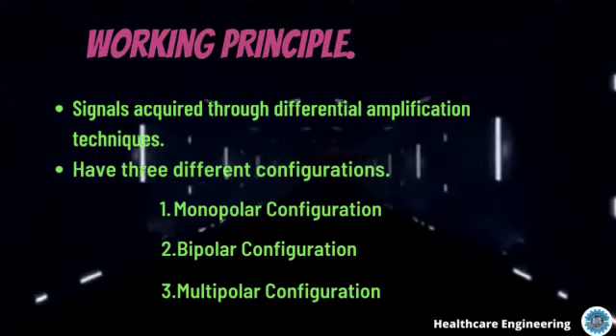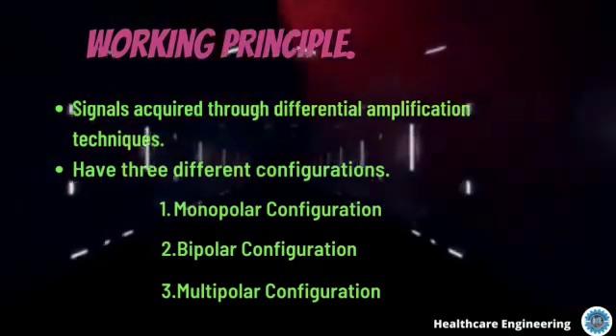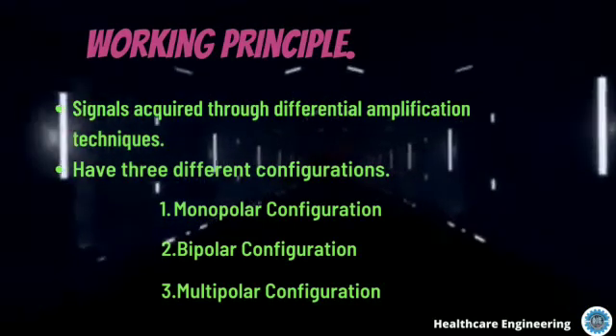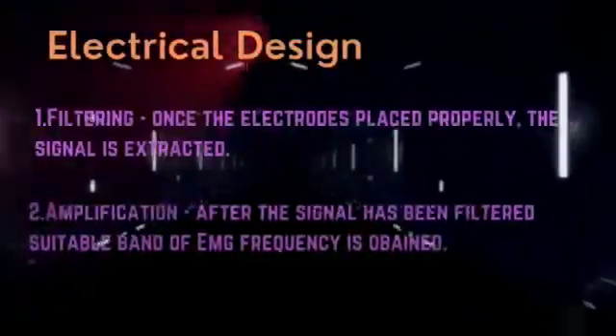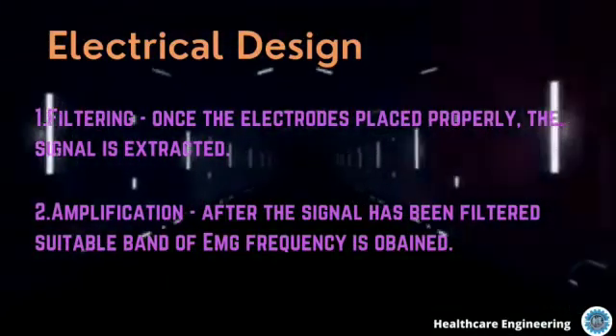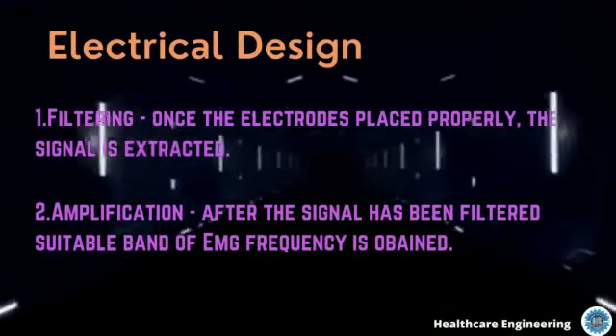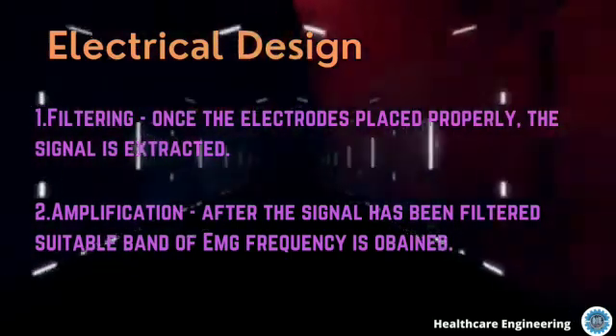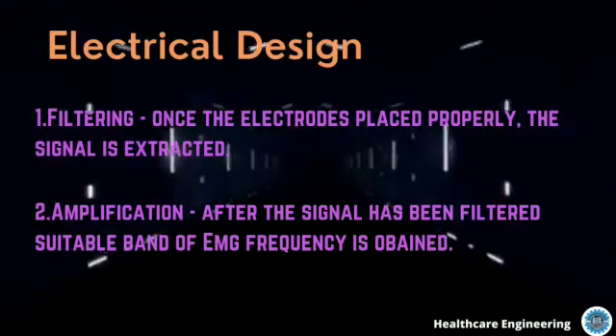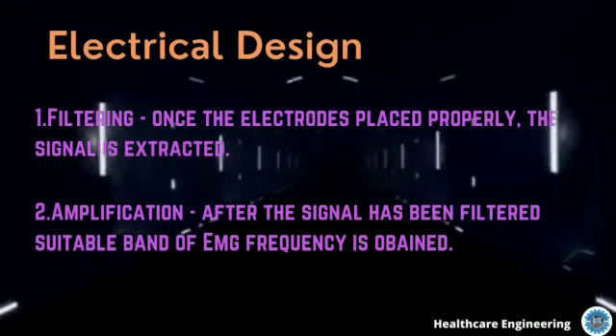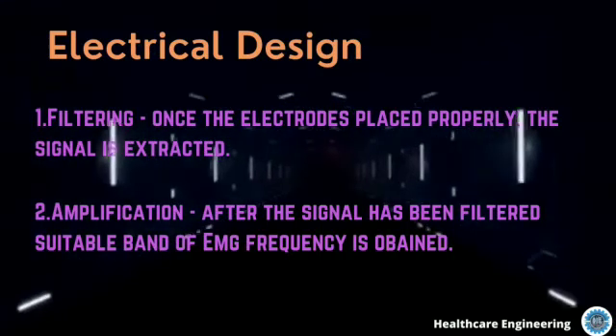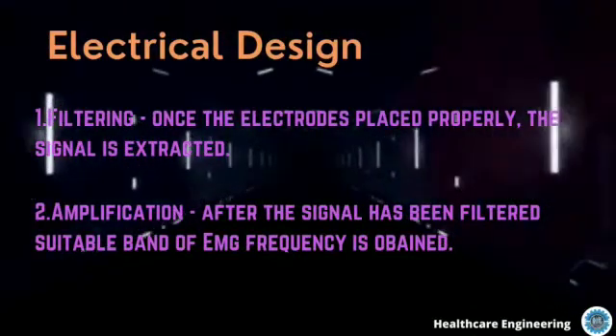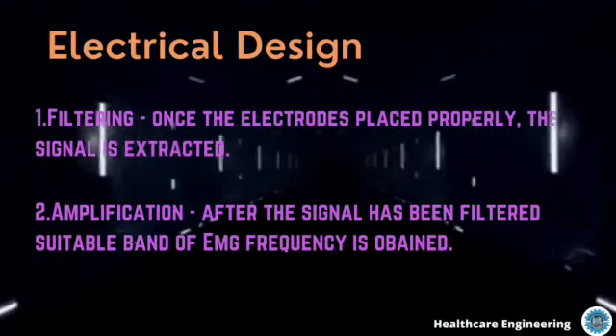Monopolar configuration is implemented using only a single electrode on the skin with respect to a reference electrode. Regarding electrical design, once the electrode is properly placed and the signal is extracted, noise plays a major role in hampering the recording of the EMG signal. For this purpose, the signal must be properly filtered even after differential amplification, using high pass, low pass, and band pass filters.